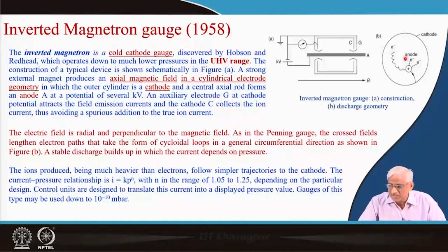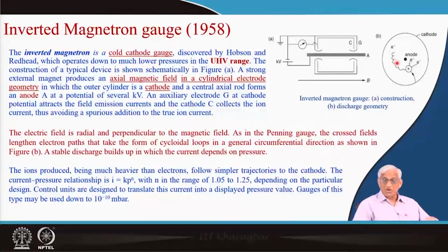So, story is same again, the starting electrons coming from this high voltage, because of high voltage field emitted electrons from the anode, they come inside, they try to produce ions from the atoms, and these ions, where will they go? Because they are heavier in nature. These electrons, because of magnetic field, they are very light, they will be precessing around that. So, they will make all sorts of loops. Okay. So, these loops, what is the role of this loop making? To increase the path length, so that more and more atoms will come for a particular structure.